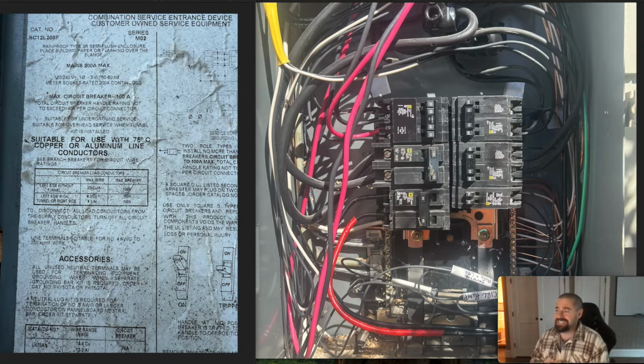So you don't really see these nowadays too often. They've pretty much been phased out. Nowadays, you mainly have a main breaker, and that's because of new code rules that sort of require that an electrician be able to de-energize the equipment they're working on. So for example, in most panels, you can de-energize the main breaker. You've got a little protective cover that covers up the hot lugs coming into that main breaker, and then there's nothing energized in the panel, so you can go in and work in there pretty safely without the threat of electrocution. Now that is not the case with these old hot bus panels.